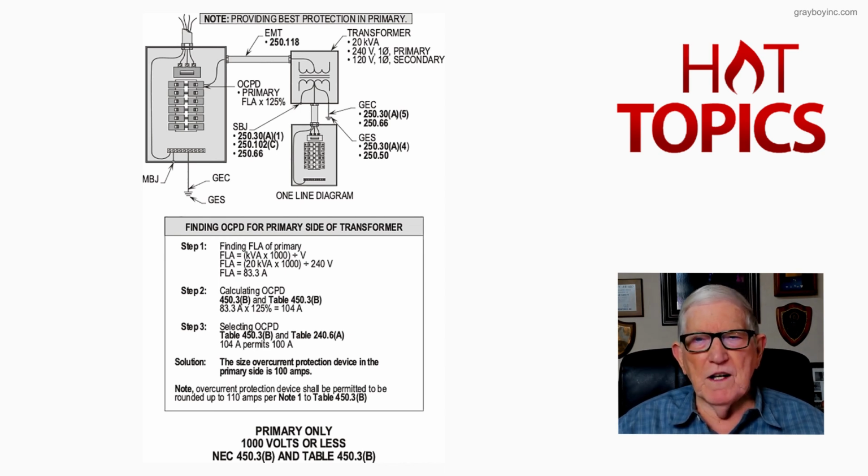You can kind of check this out. Notice these are good rules of thumb for that inrush current out in the field. Mostly separately derived systems, whether it's a special type system, will never usually be above 12. But this is how you could calculate it to get a good rule of thumb. Then you'd want to see, is it 0.1 second, 12 times usually max, or 1 second where it would be over 12 up to 25 times in some cases. So just keep that in mind, and that's what this figure 11-6 is illustrating to the user of the NEC.